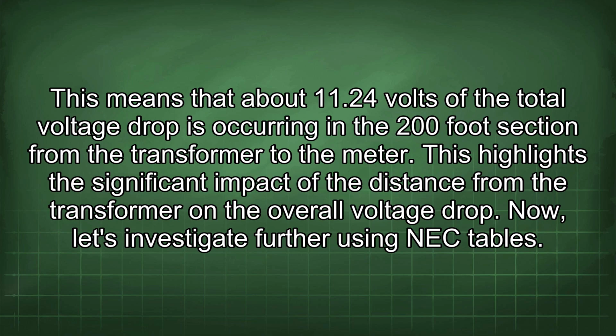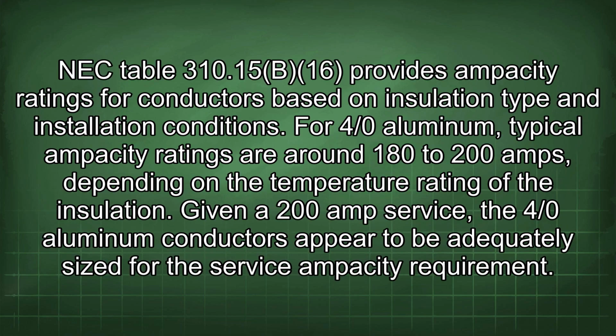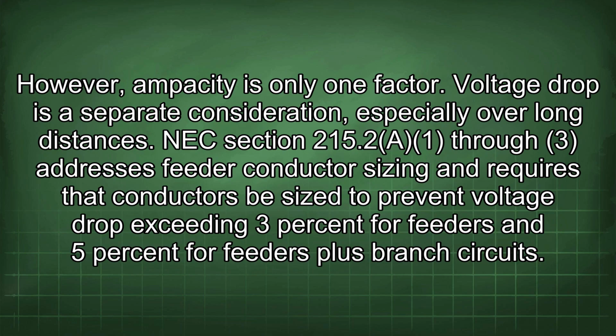Now let's investigate further using NEC tables. NEC Table 310.15(B)(16) provides ampacity ratings for conductors based on insulation type and installation conditions. For 4/0 aluminum, typical ampacity ratings are around 180 to 200 amps, depending on the temperature rating of the insulation. Given a 200 amp service, the 4/0 aluminum conductors appear to be adequately sized for the service ampacity requirement. However, ampacity is only one factor. Voltage drop is a separate consideration, especially over long distances.